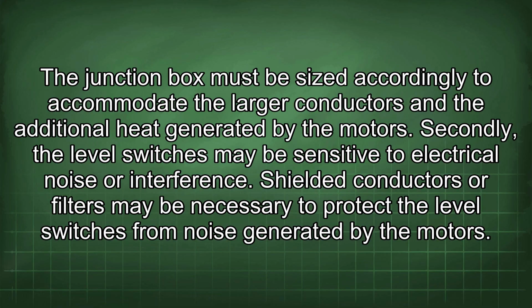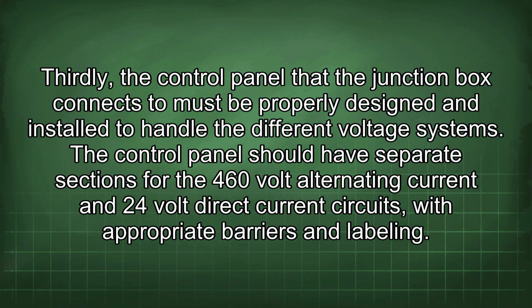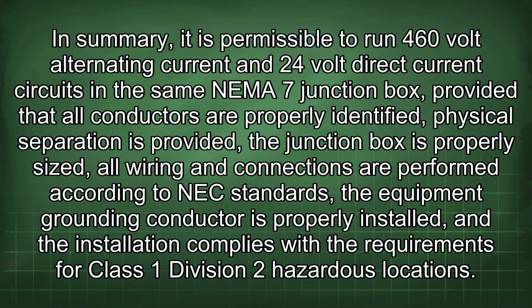Secondly, the level switches may be sensitive to electrical noise or interference. Shielded conductors or filters may be necessary to protect the level switches from noise generated by the motors. Thirdly, the control panel that the junction box connects to must be properly designed and installed to handle the different voltage systems. The control panel should have separate sections for the 460-volt alternating current and 24-volt direct current circuits, with appropriate barriers and labeling.